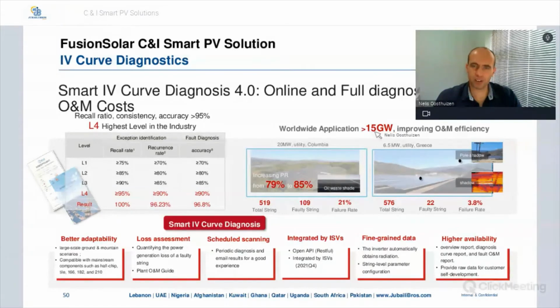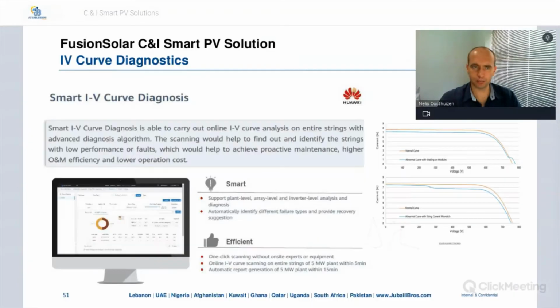Worldwide application is greater than 15 gigawatt. Advantages of the smart IV curve diagnosis are better adaptability, loss assessment, and scheduled scanning. On the scheduled scanning, you can schedule it weekly or monthly, and then have the reports auto-generated. So by the time you have a meeting or something, all of that information is available. It's integrated by ISVs. You get fine-grained data, and you've got higher availability of the system.